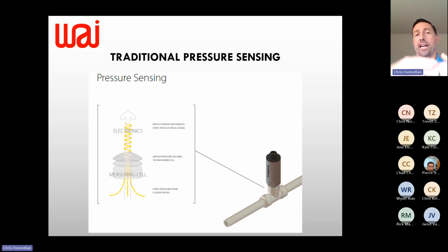That cell basically has a strain gauge on it. So as that media pushes up, the cell is going to flex, and that's going to be either a ceramic cell or a stainless steel cell. There's different properties of that cell or diaphragm that would make one desirable over the other. But the technological premise is you've got some flexing, with a strain gauge on the back of that.